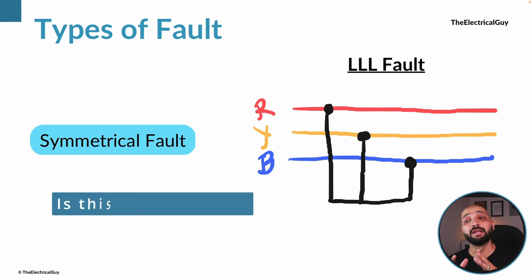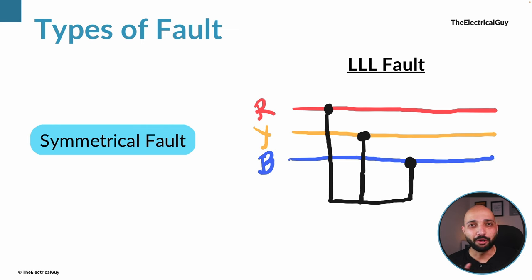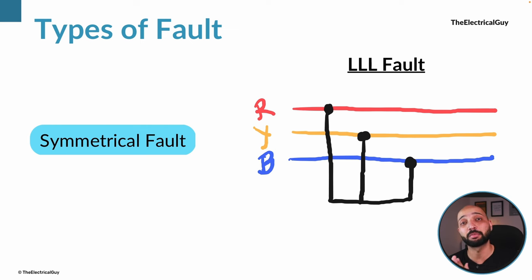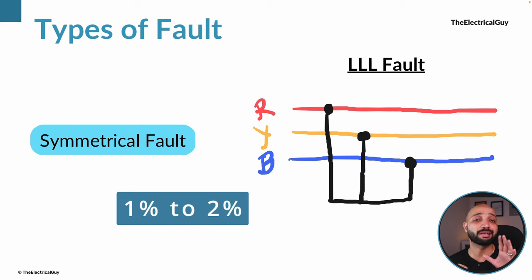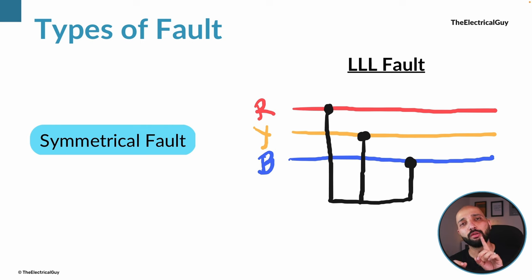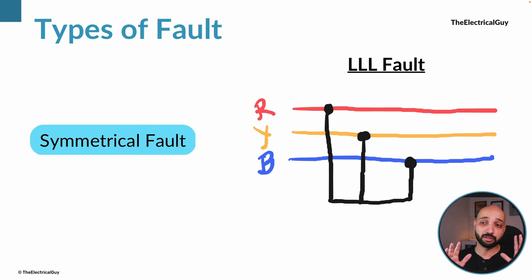You may ask: if in a symmetrical fault the system is still balanced, does that mean it's a good fault? No — no fault is good. The triple line fault is actually the most severe fault a power system can witness, and the rating of circuit breakers is decided based on this fault in most cases. However, the occurrence of this fault is very rare — only one to two percent of faults are symmetrical in nature.